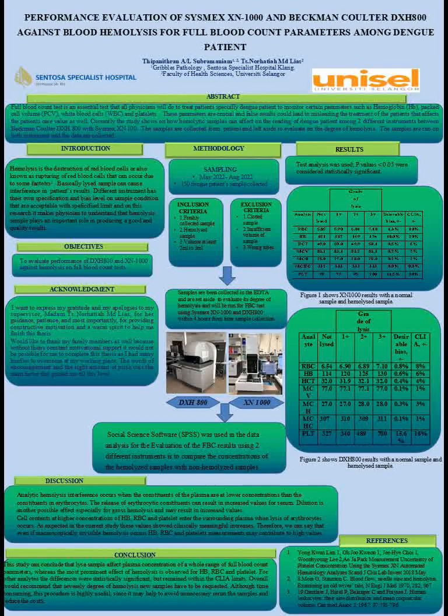This was taught by one of my HODs in the hematology department, that we use CLIA to have a range of the acceptable bias that is produced by the machines themselves. So, for example, for XN1000, I have divided it into the parameters, which are RBC, HB, PCV, HCT, MCV, MCH, MCHC, and platelet, and the results are more significant as the lysis increases.